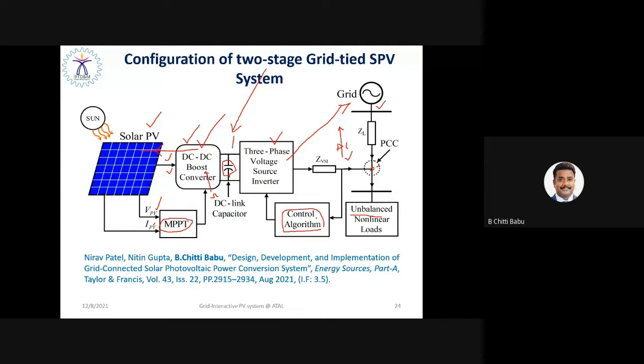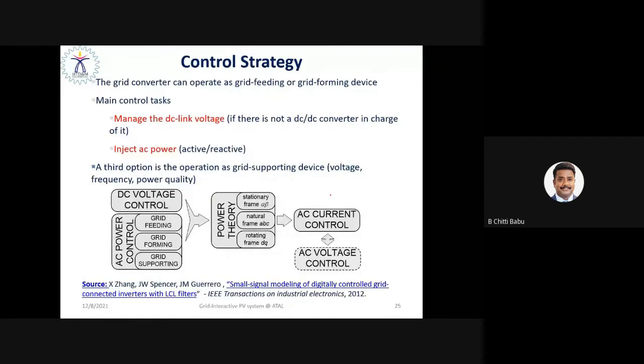So the control algorithm we employ on this three-phase PWM voltage source inverter has to provide proper grid connection requirements. I mean, the control algorithm has to maintain the voltage profile constant, and has to maintain the grid frequency constant. In order to maintain the frequency and voltage, active and reactive power must be controlled independently. In addition to that, the inverter output frequency and grid frequency both must be synchronized by properly estimating or sensing the fundamental frequency component. All right. Yes, that is how the control strategy is going to be implemented.